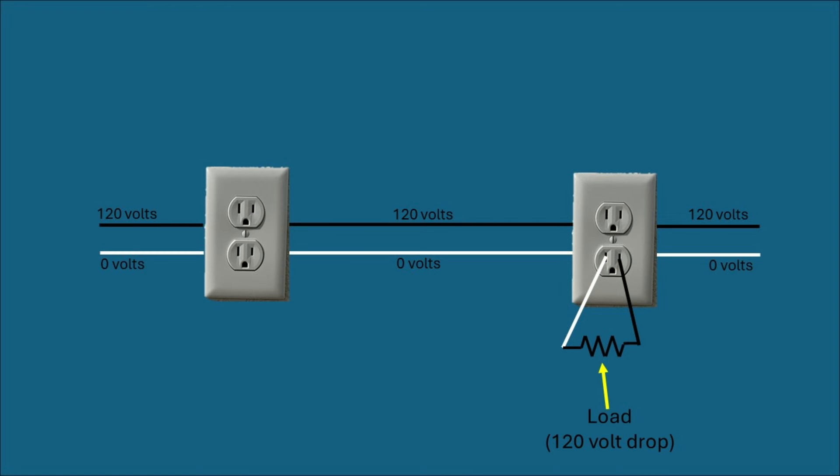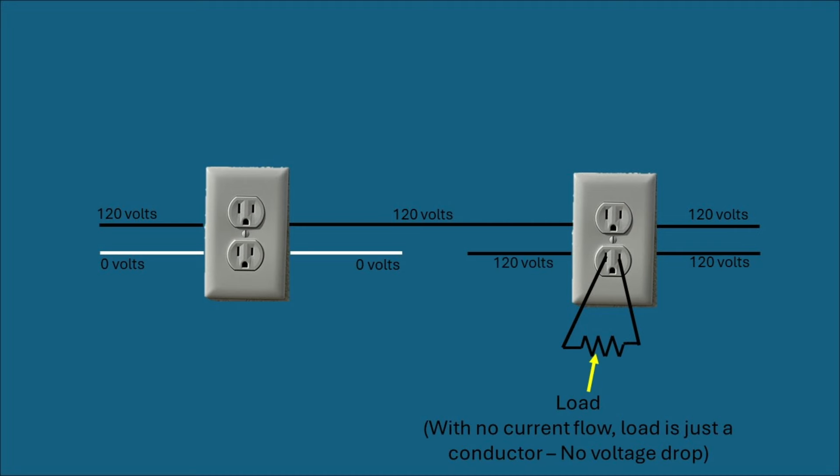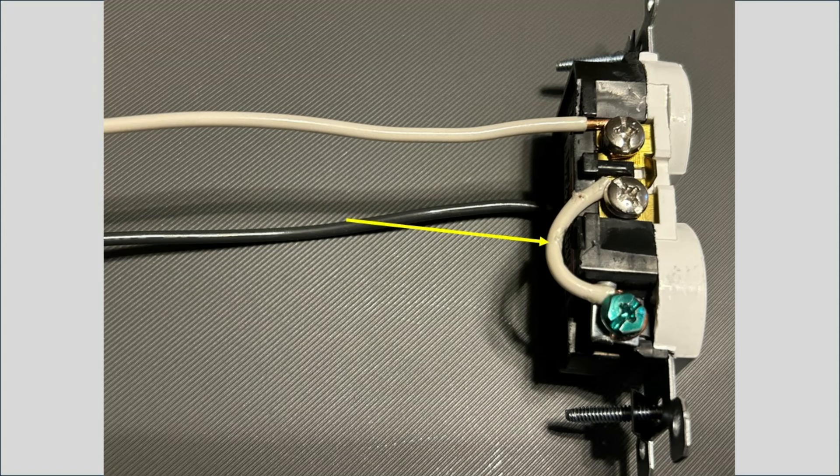So now let's look and see what happens when the neutral is opened. With an open neutral you still have that load plugged in but current can't flow. So that load is just like a conductor. There's no voltage drop. So you'll have 120 volts even on the neutral wire at that receptacle. And on a bootleg ground you've got the ground screw and the neutral screw connected together. That means you're also going to have 120 volts on that ground screw.